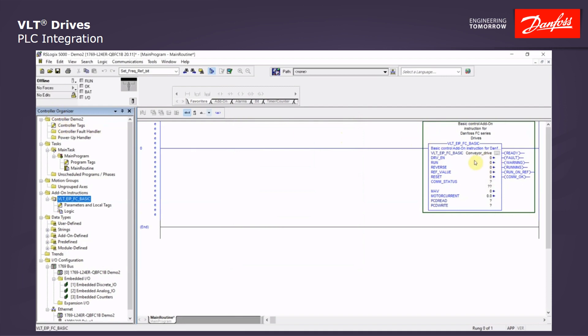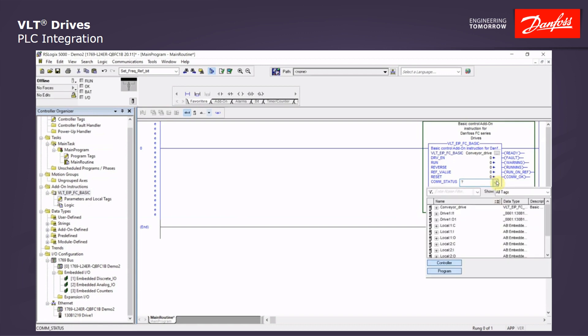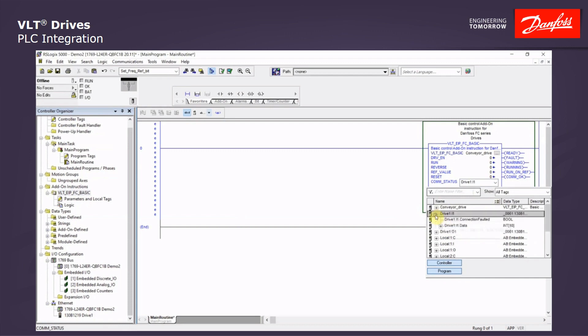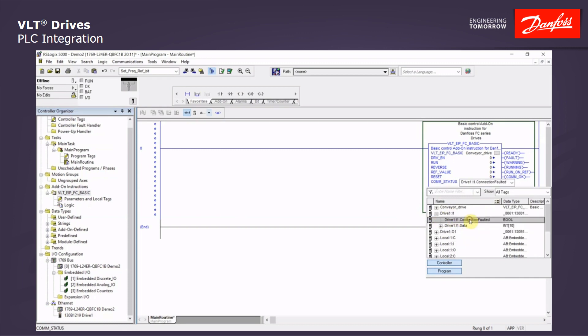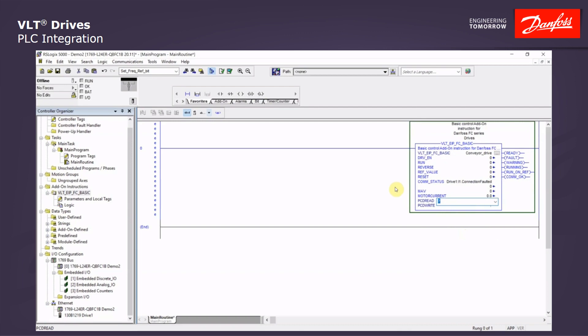Now all the tags are created up in the controller tags. Now the only thing left for us to do is to link the comm status and the PCD data read to the drive we created down in the ethernet connection, drive 1. So the first question mark under comm status, we will double click, click the down arrow, and it will open up the controller tags. And we see drive 1, input. And we click the plus to drop it down and we will double click the connection faulted. Click OK.